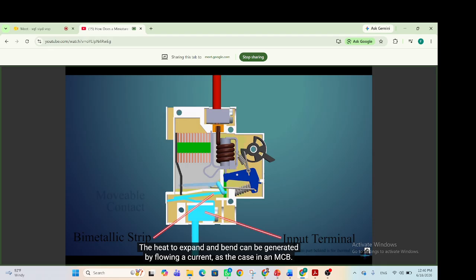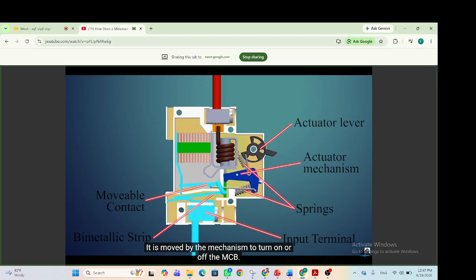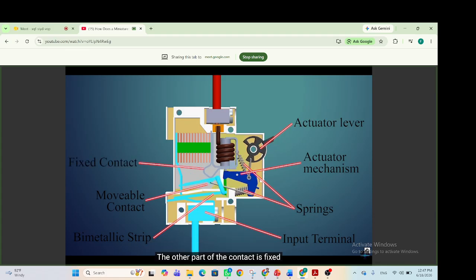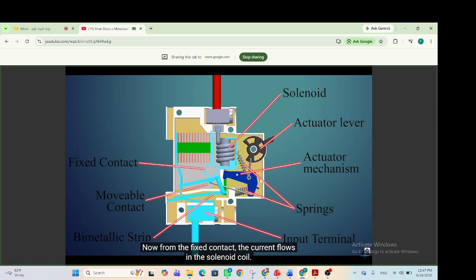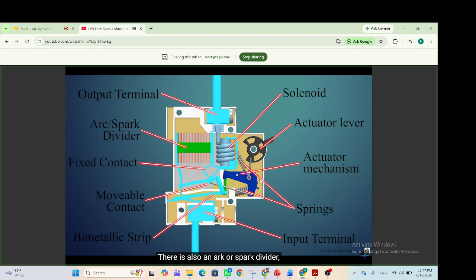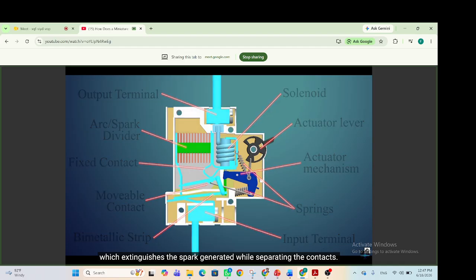Then we have the movable contact. It is moved by the mechanism to turn the MCB on or off. The other part of the contact is fixed. From the fixed contact, the current flows into the solenoid coil. This solenoid coil creates a magnetic field that pushes a plunger with a pin as required. Then we have the output, which goes out to the appliances. There is also an arc or spark divider, which extinguishes the spark generated while separating the contacts.